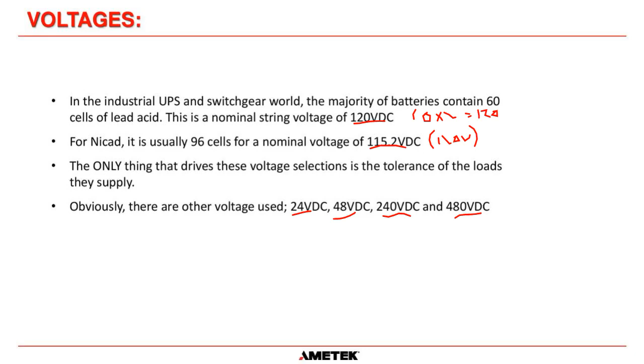So, as I said, the load circuit tolerances are what drives the selection of batteries. For a 60-cell lead-acid system, the float voltage is approximately 135 volts, and we'll go into that in just a moment. But most people recognize that it's 2.25 volts per cell. That is the float charge required for a lead-acid battery, roughly. And 2.25 times 60 is equal to 135.